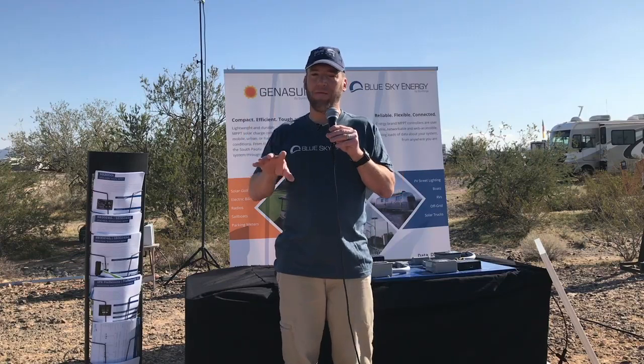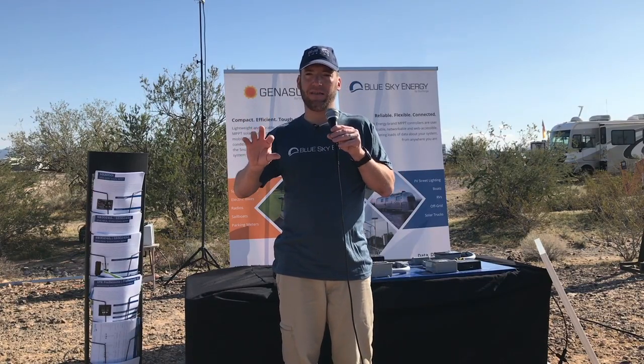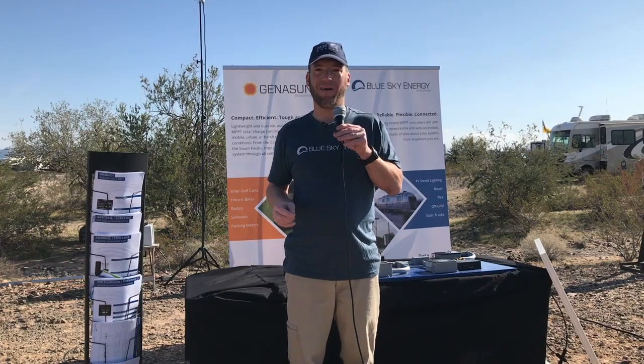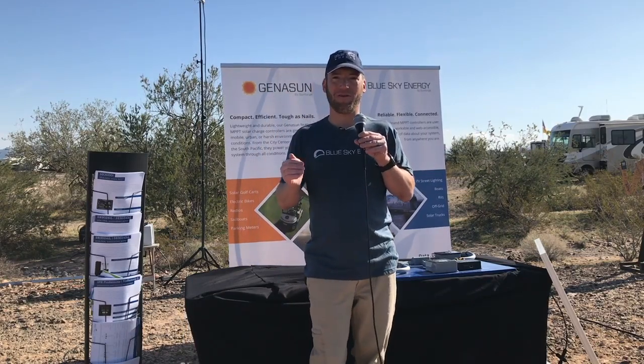I found that at a 5 amp load, their disconnect voltages didn't quite agree with what I was observing as far as the state of charge left. So we played with it a few more times, and I'll be happy to forward you what I discovered on my personal testing versus an LVD cutoff switch for the Dragonfly. But that could have just been a load difference. They might have had a 1 amp load on their battery, and that would affect the cutoff voltage versus the capacity or state of charge of the battery where it was left. But it was consistent, and I did get 100 amp hours out of it every single time before it turned off, so I was impressed by that.